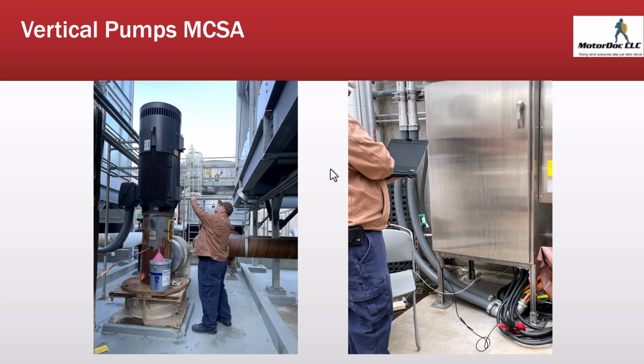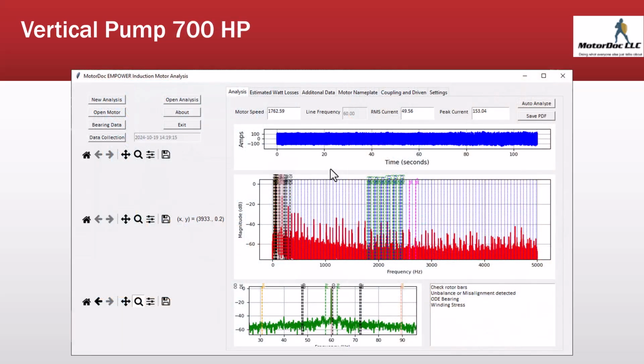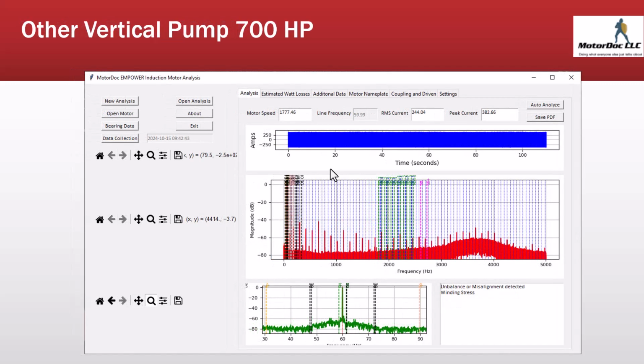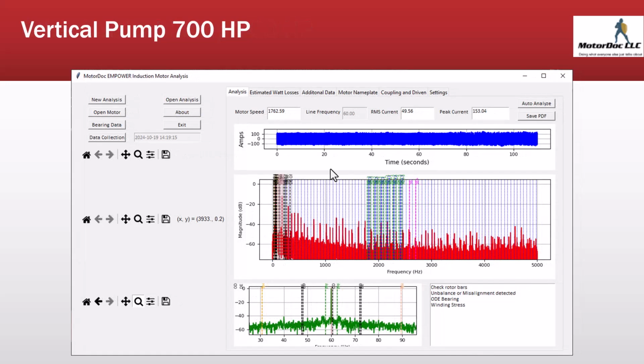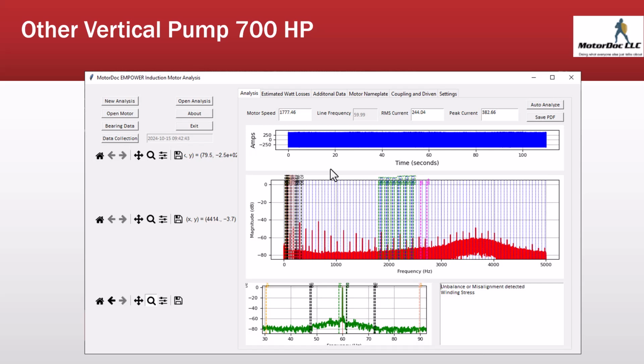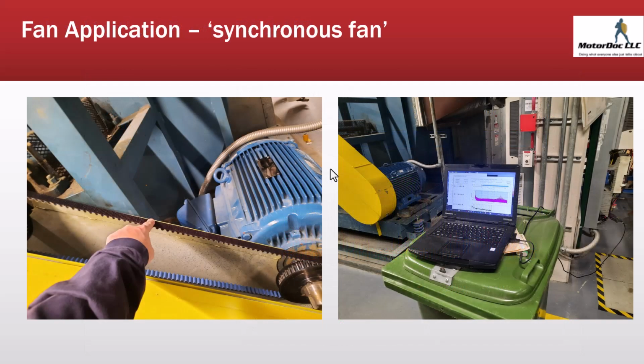This is a vertical pump. We take a look at this. This was one that was having problems. We were able to identify immediately the reason it was tripping had to do with bearings, the opposite drive-end bearing, and improper settings in the drive, which causes winding stress. You can see that again here. I see that one an awful lot, and that basically has to do with the settings.